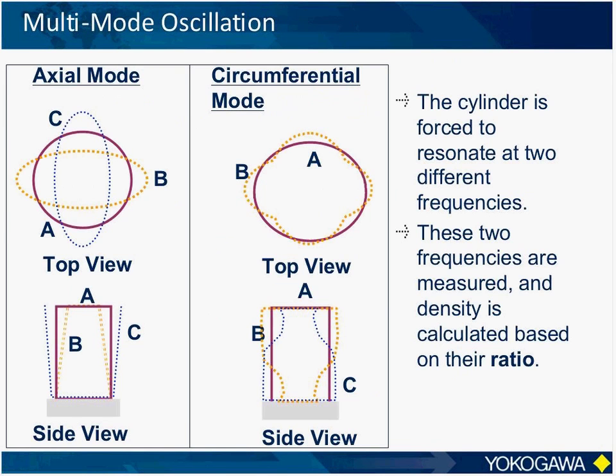Now, some vibrating elements utilize what we call a multi-mode oscillation. In these systems, the cylinder is forced to vibrate in 2 different modes, an axial mode and a circumferential mode. Now, this, of course, results in 2 different frequencies that are measured, and the density is then calculated not by the magnitude of the frequencies, but by their ratio. Now, as the gas density increases or decreases, this ratio between the 2 frequencies will also increase or decrease.